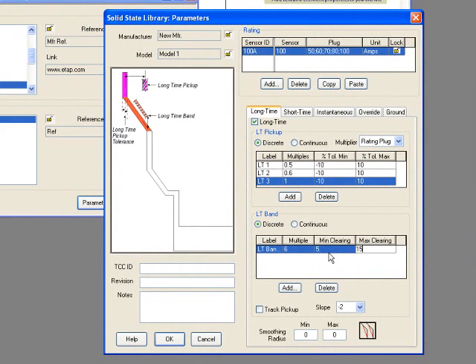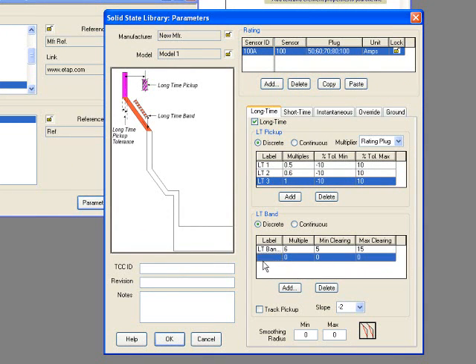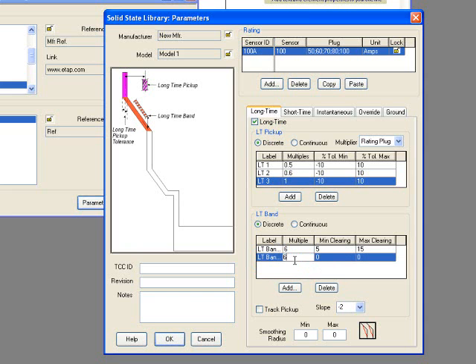Add the next Long Time Band. In this case, you'll have three Long Time Bands. LT Band 1, 2, and 3. They can be the same multiple, but in the minimum clearing and maximum clearing, they will be different.